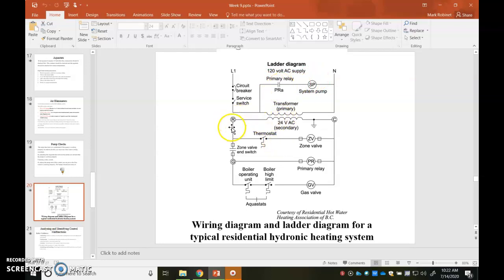Underneath that, it's a little different. You'll see a thermostat. And a thermostat on a boiler is not always identified as R and C, although this one is with an R and a C. But sometimes identified as T and T, which means thermostat and thermostat. Obviously, we don't need other letters because you can't put air conditioning on a boiler.